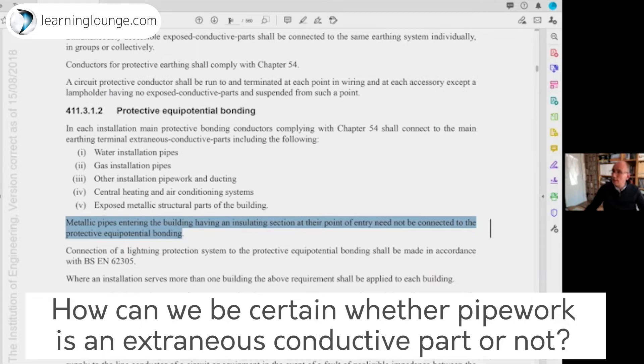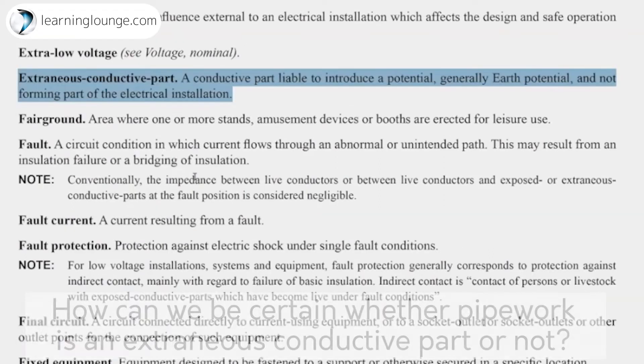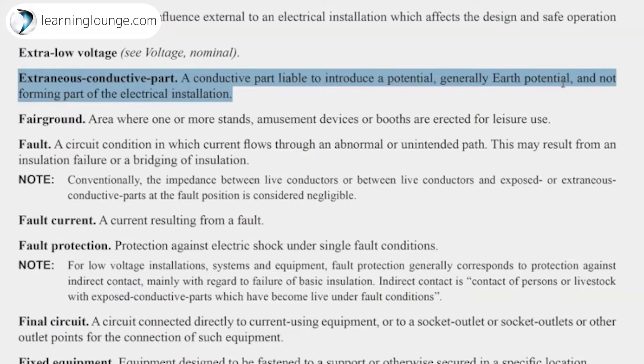The question would be how do we absolutely be certain that something is or isn't an extraneous conductive part, because that can be the exception. I'm going to take it to the next regulation to cover that, here in part two. It is a conductive part liable to introduce a potential, and that is generally earth potential, and it is not forming part of the electrical installation. So this could be a metallic pipe or a ducting from the outside. It could be steelwork coming out of the ground for a large building. If there were to be a fault and the part became live and you touch that metalwork, you would get an electric shock, so we need to bond that.